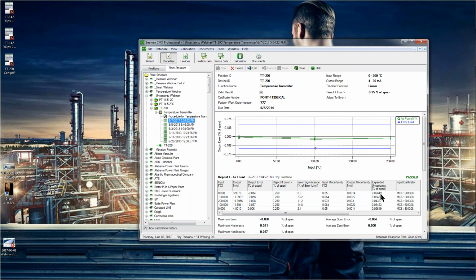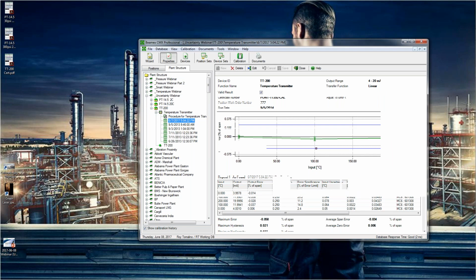The expanded? Yeah, what's the highest value in that column? Oh, the midpoint, 0.04327. So if you take your 0.25 and divide by 0.04, you've got like a 5-to-1 test uncertainty ratio, better than 5-to-1. And as you said, graphically you can see that little guard band is 1/5 of the blue line that we're trying to get in the process. So that helps pull what I presented together a little better.